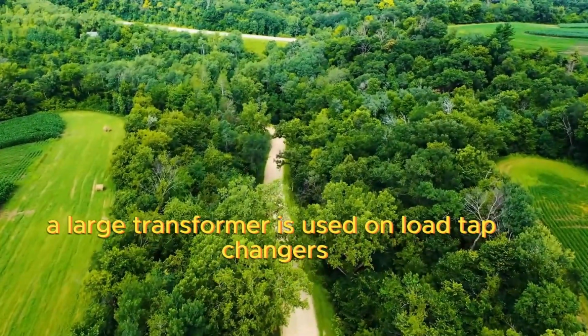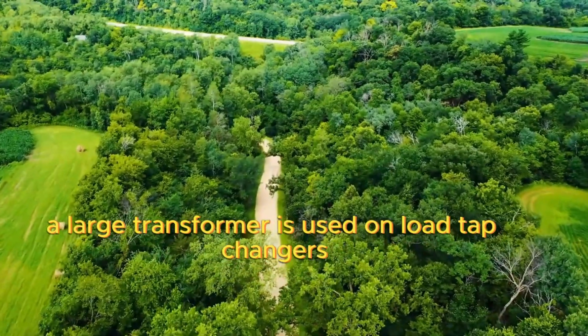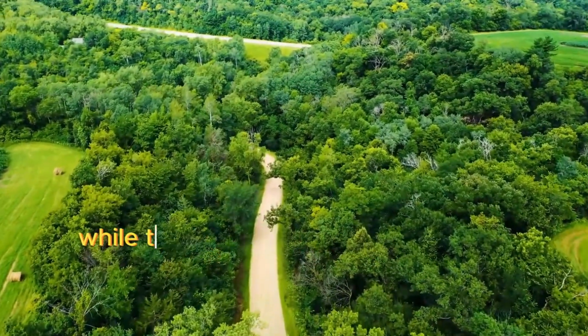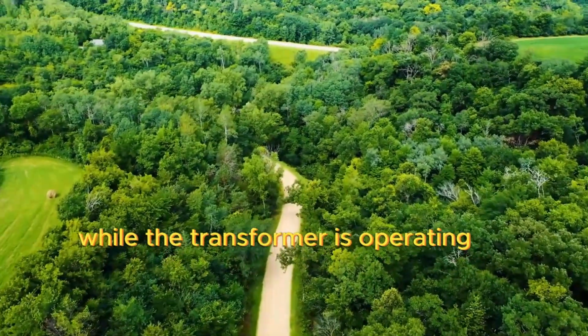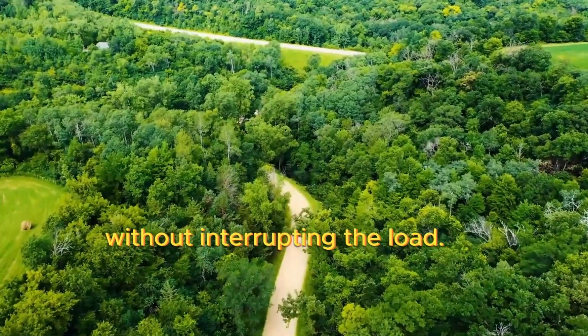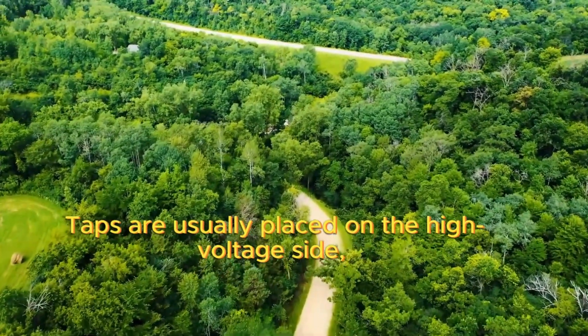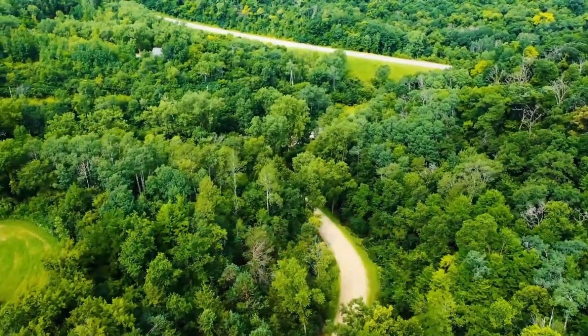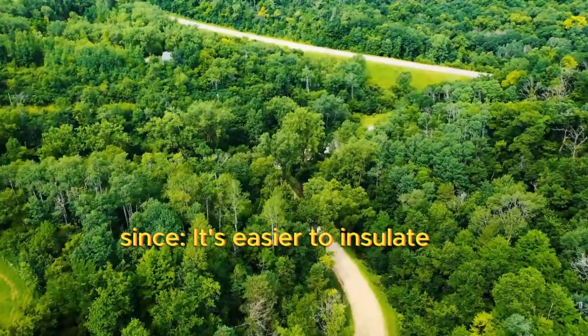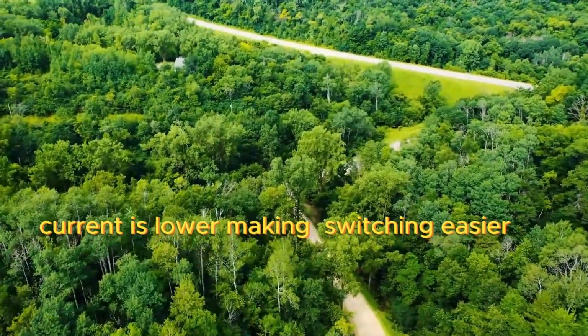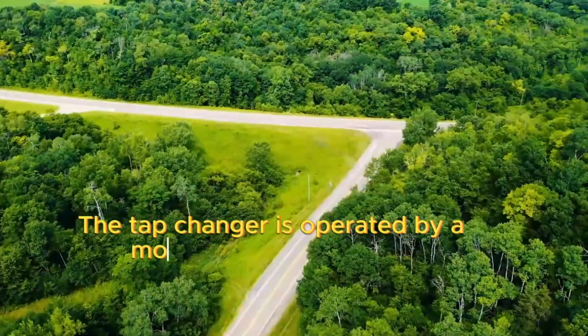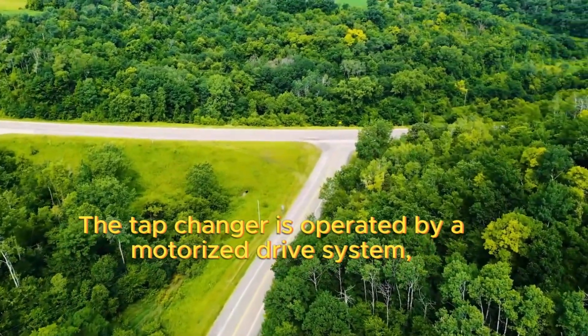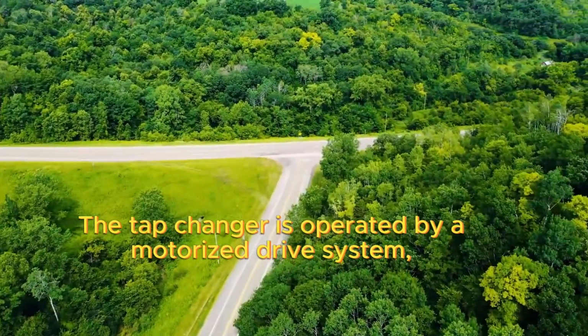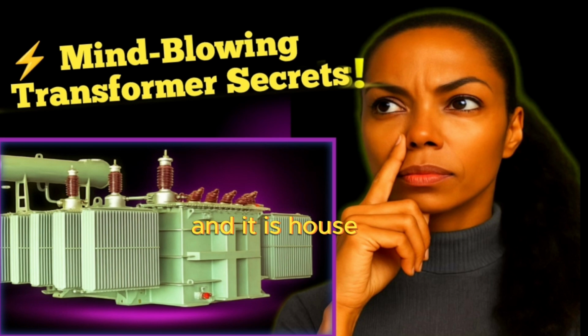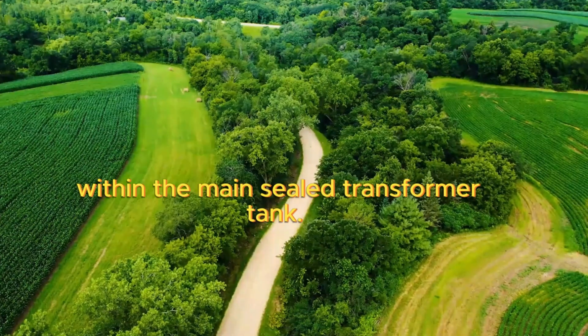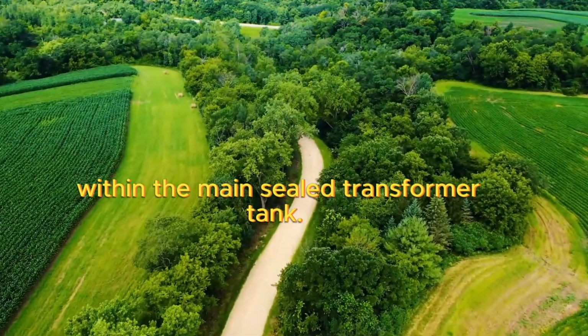Large transformers use on-load tap changers, which adjust voltage while the transformer is operating without interrupting the load. Taps are usually placed on the high voltage side since it is easier to insulate, current is lower, and switching is easier. The tap changer is operated by a motorized drive system and it is housed within the main sealed transformer tank.